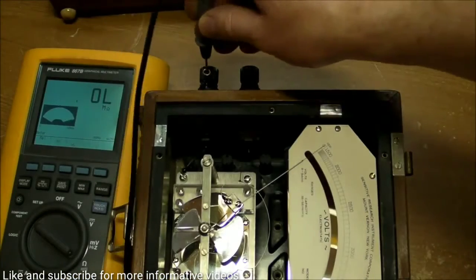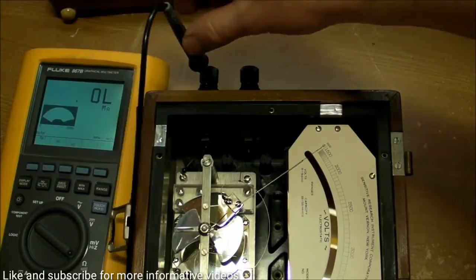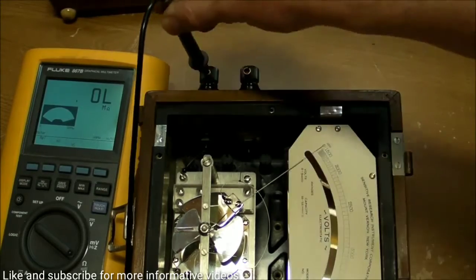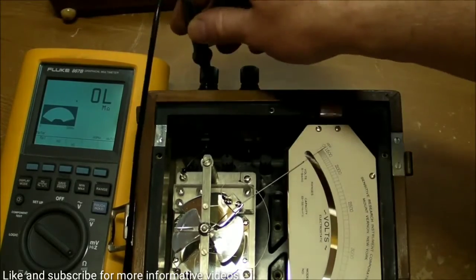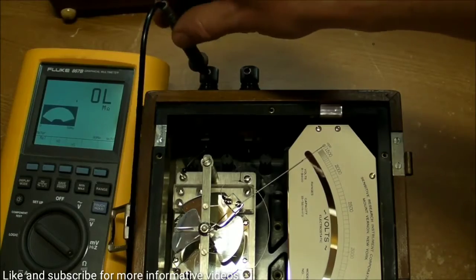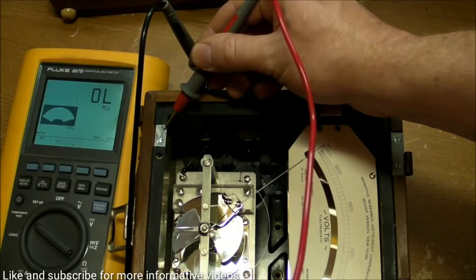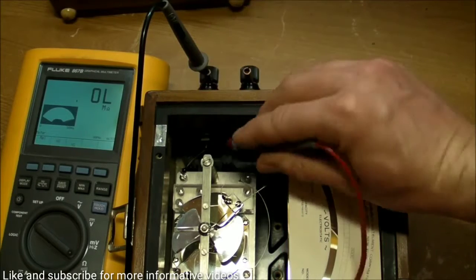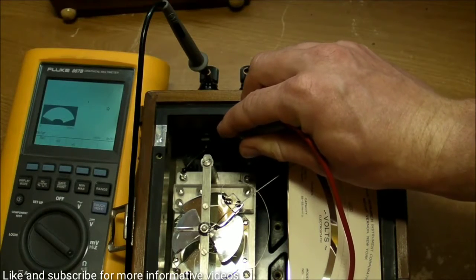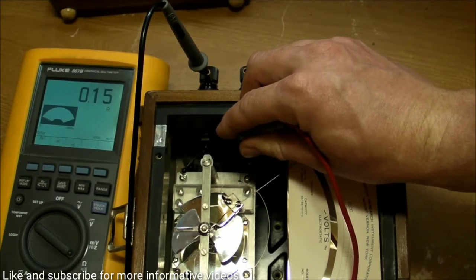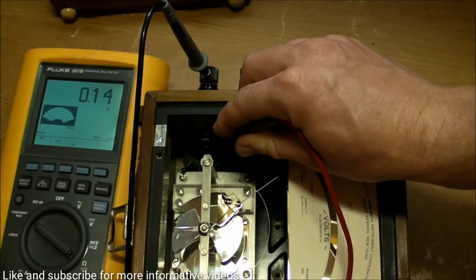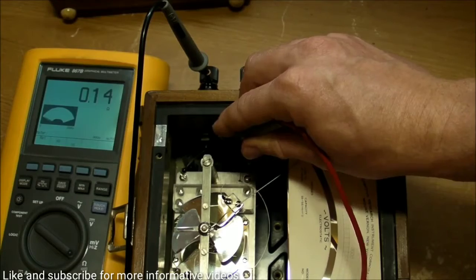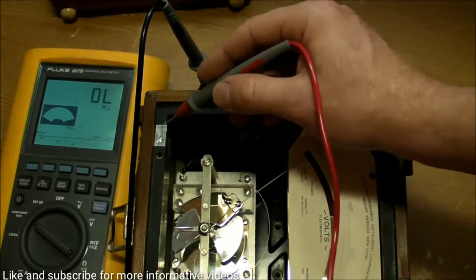So let's measure some resistance here. I'll plug this straight into the low side or the ground. I don't really have to hold it down. It's just touching the copper. That's going to be a low enough resistance compared to everything else right here. Because if I just touch it here, there's nothing. And I can touch it down here to the ring where this thing is connected. There we go. We got 0.15 ohms. So clearly a pretty good connection with the black probe.